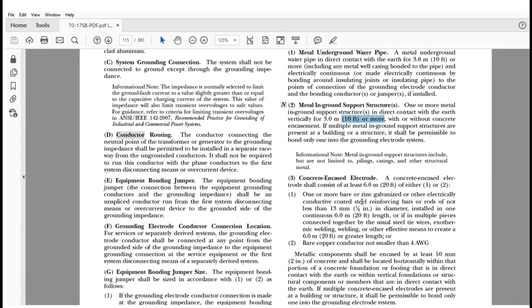The importance of this is to remember that we just talked about the building framing. That can be utilized when that connection is made to extend the connection to the grounding electrode system, or treated like a conductor in 250.68(C)(1) and (2). Whether we're dealing with a water pipe or this type of application here. It also goes on to add an informational note that says metal in-ground support structures include, but are not limited to, pilings, caissons, or other structural metal that can meet this requirement. So it adds a little bit of clarity to what people previously called the metal frame of a building, and there were a lot of arguments about what would constitute that. Hopefully, if you have any questions, for brevity and time, I want to make sure we cover all of these as possible.